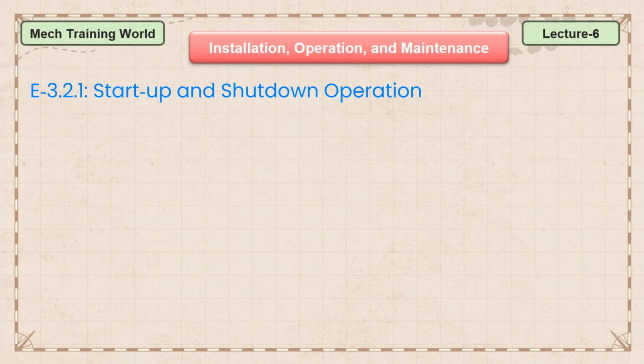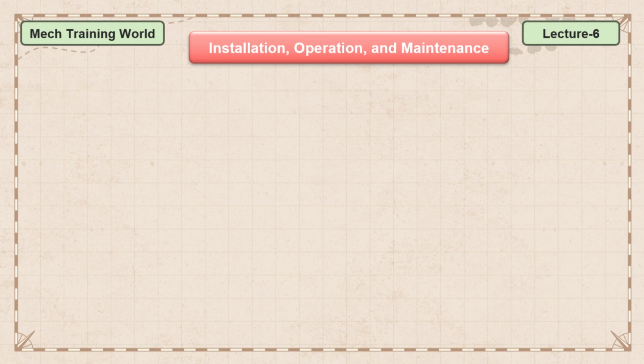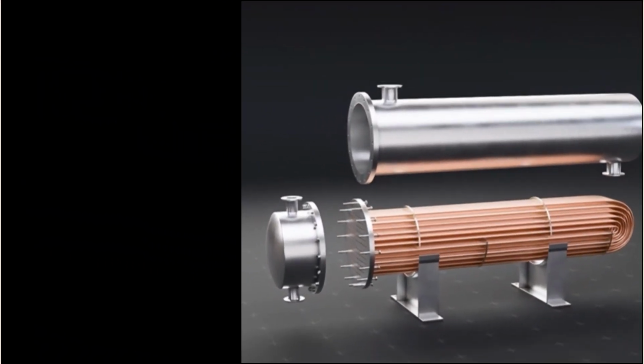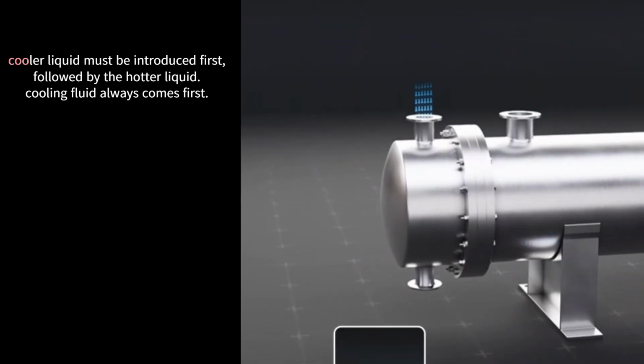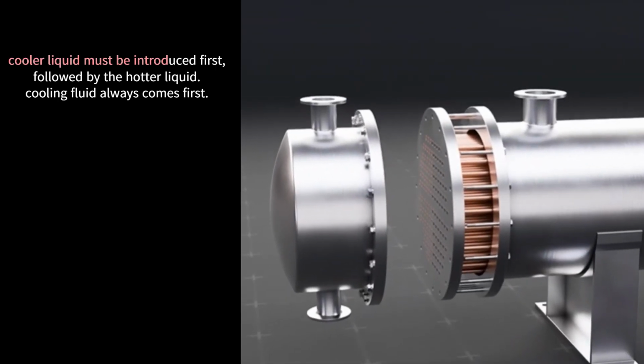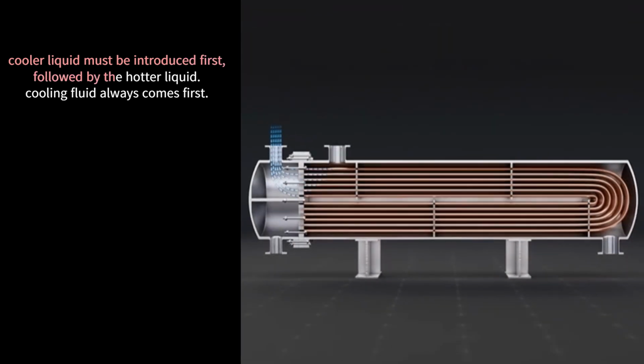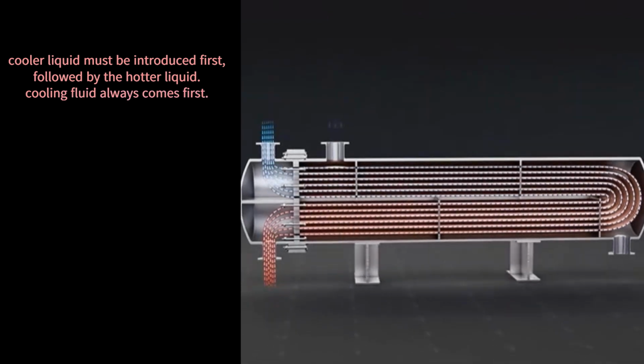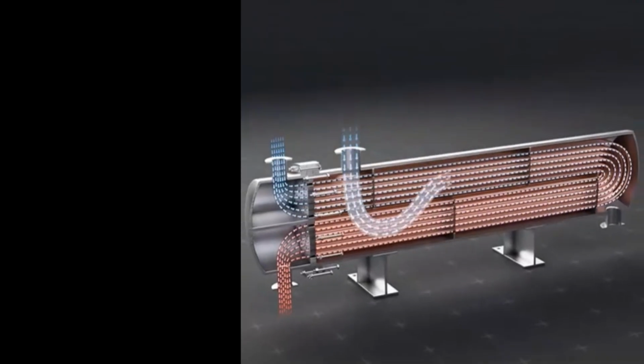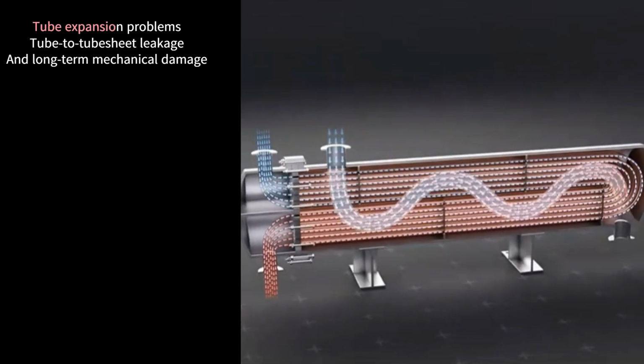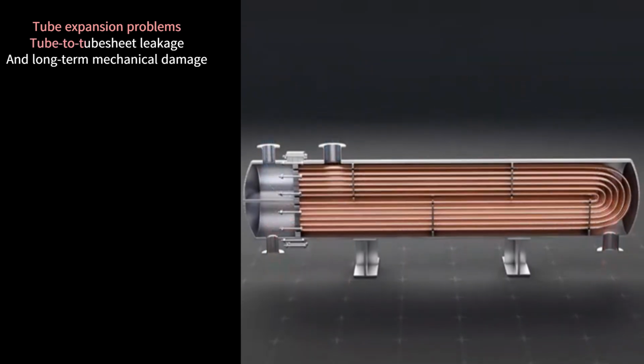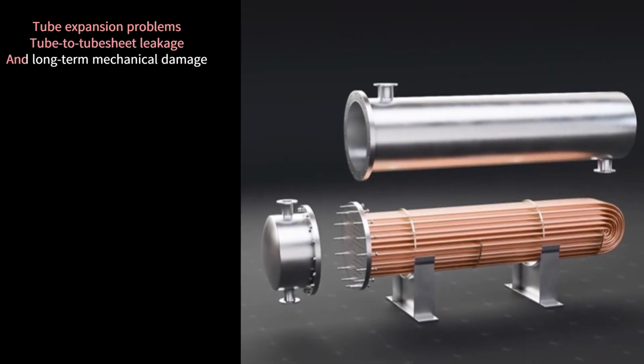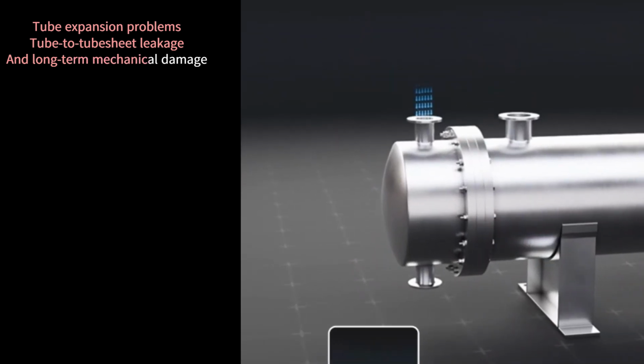Next, let's talk about startup and shutdown operation, which was provided in E 3.2.1. During startup, the rule is simple but very important. The cooler liquid must be introduced first, followed by the hotter liquid. Even if the hot fluid flows on the tube side and the cold fluid on the shell side, cooling fluid always comes first. Why? Because introducing hot fluid into a dry or cold exchanger can create thermal shock, leading to tube expansion problems, tube-to-tube sheet leakage, and long-term mechanical damage.